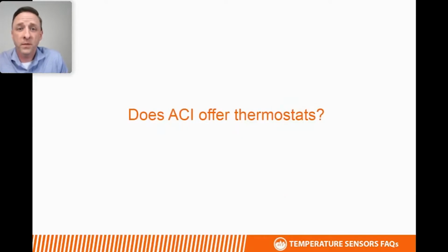Does ACI offer thermostats? No. All of our products are technically sensors, so they don't offer any control or switching mechanism built into the sensor itself. They're all designed to produce a stable or continuous output back to a control system that interprets that output. For lack of better terms, our sensors are dumb. That just means they're just outputting a signal, and another device is used to interpret that signal to determine when additional heating is needed or when additional cooling is needed, and down that line.